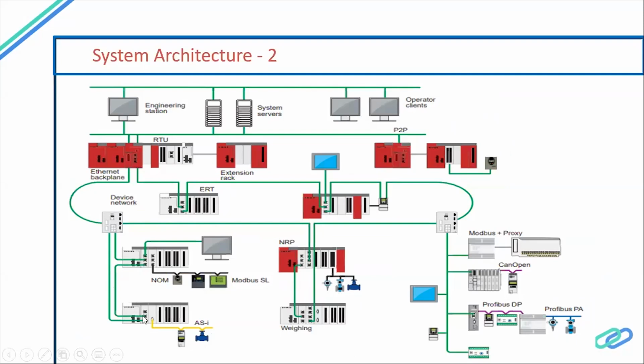So these are redundant networks. Just to see, the ring network is there. If maybe one network has failed, it automatically switches to another network. So this is your HMI, and this is your NOM module, and this protection relay, this is energy meter. These are all communication devices, because communication devices are always connected on a daisy chain only. So if you are reading devices, you need to connect a maximum of 16 devices for reading purposes in one network.